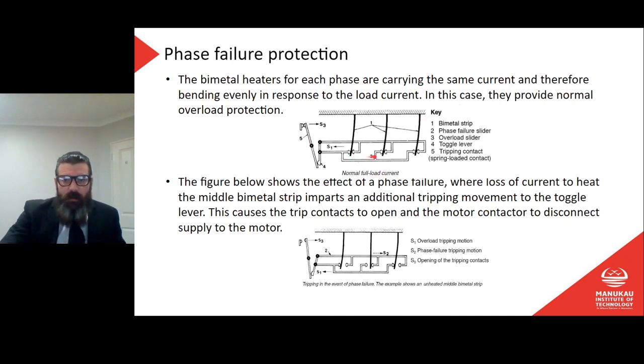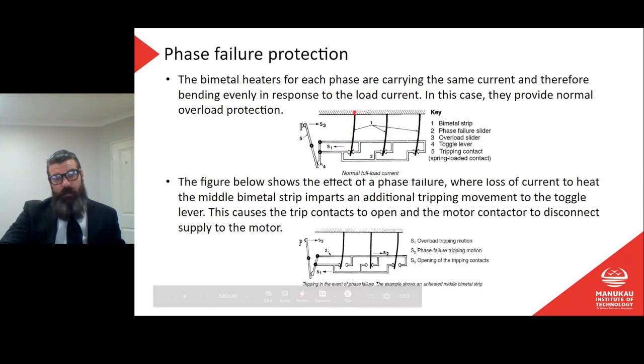Here we have that. Here are our bimetal strips. Right, and then as current is going through, they're going to bend, but they'll bend the same. The figure below shows the effect of a phase failure, where loss of current to heat the middle bimetal strip imparts an additional tripping movement to the toggle lever. This causes the trip contacts to open and the motor contactor to disconnect the motor supply. So that's worth noting there, right? We can see the bend in this one here. That means as it heats up, it's bending this way, so the bottom of it here is moving to the left. And they're all moving in sync with each other, which is fine.